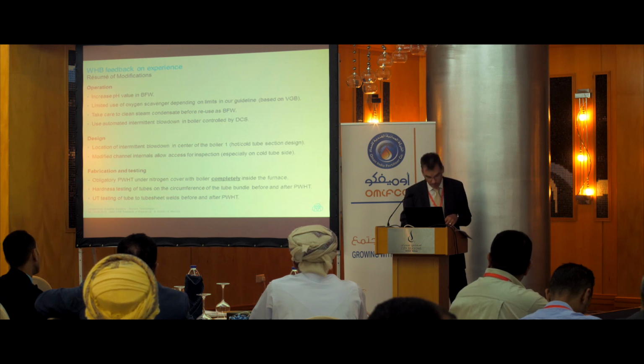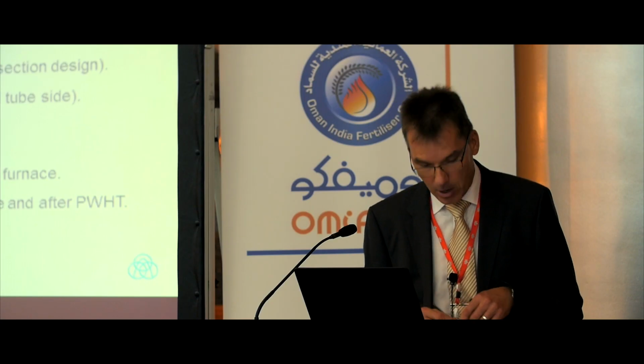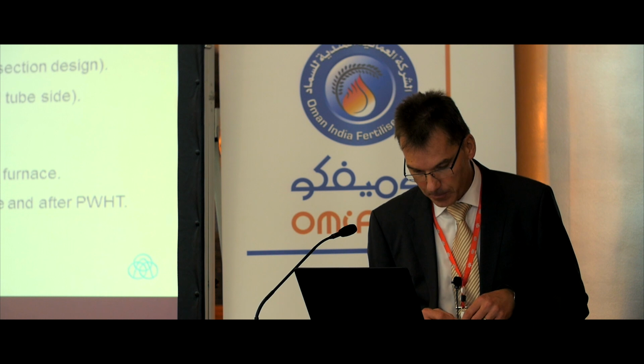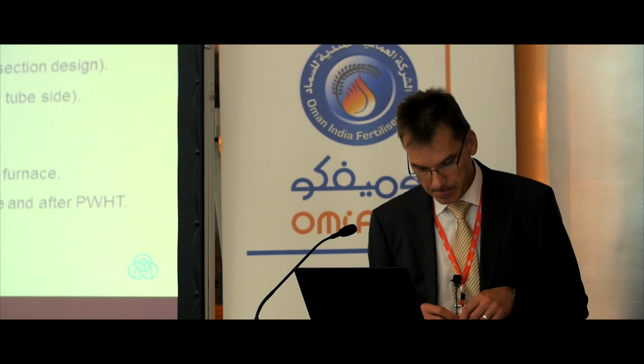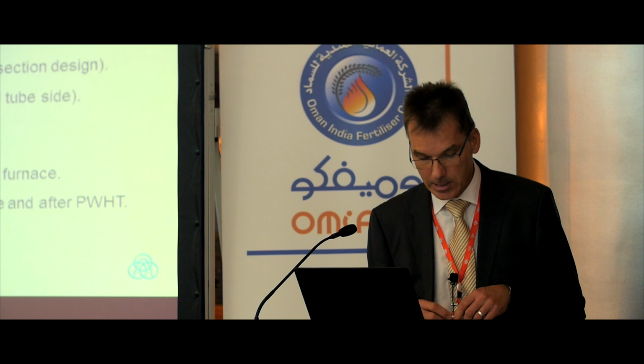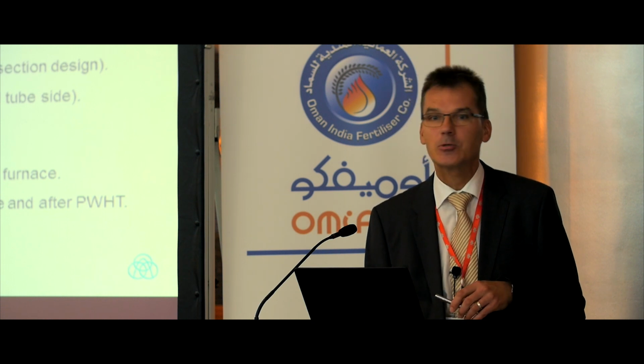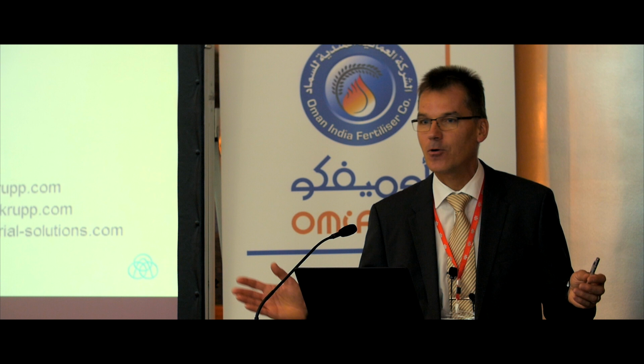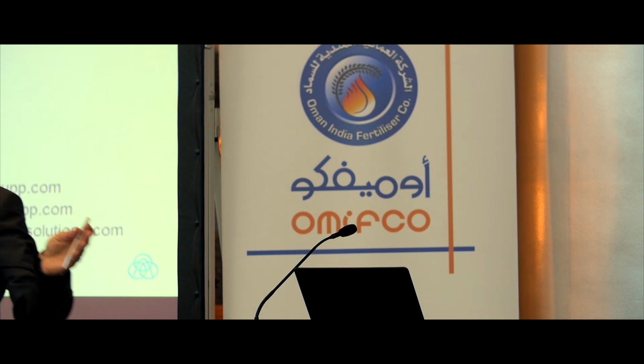It looks simple, but it was a long way to go with a lot of parties involved. And in my impression, if plant operators keep an eye on the boiler feed water quality and correct blowdown operation, and manufacturers follow our stringent requirements for quality, then boilers should operate many years without leakage problems. Thank you. The slides end the presentation. I'm happy for questions. Otherwise, I'm available for the next 2-3 days. If not, then thank you again.